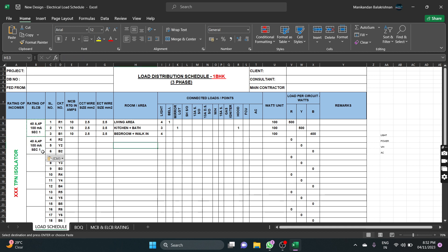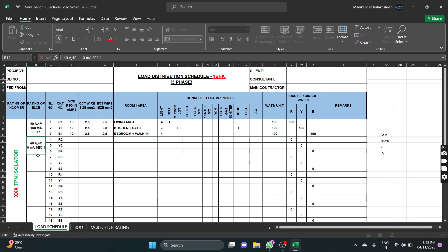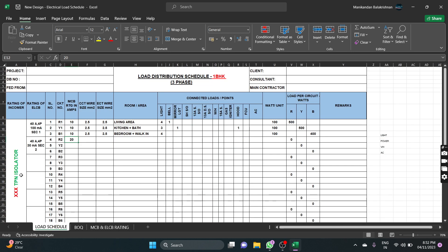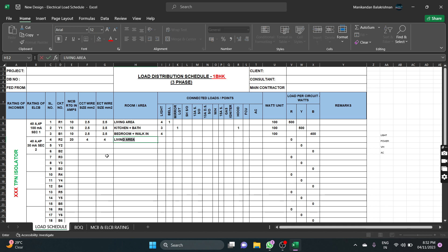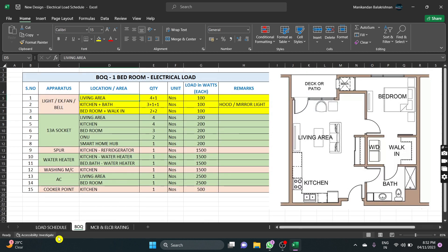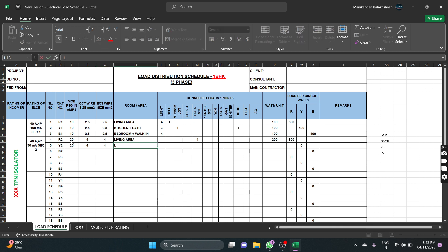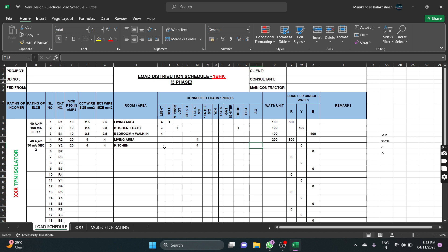Section for light: the ELCB is 100mA. For the power section, the MCB rating is 20 ampere with 4mm² cable. For living area power, there are 4 single circuits each at 200W. The same order applies for kitchen area — 4 circuits. Kitchen and bathroom: bathroom is 4 circuits, kitchen is 4 circuits at 200W each.